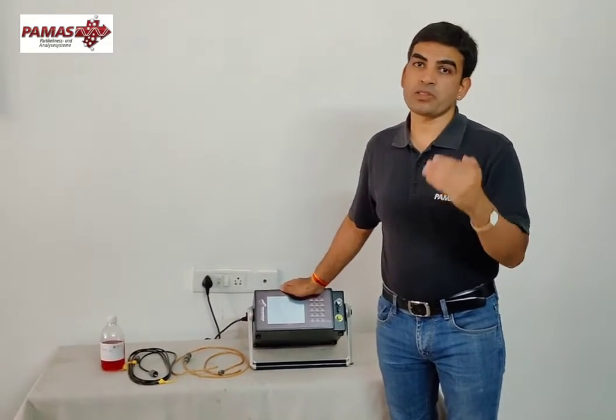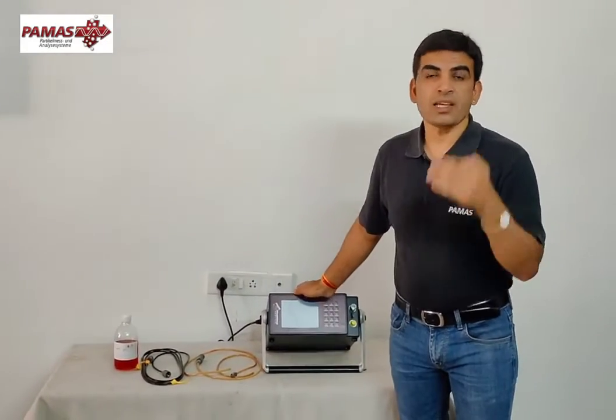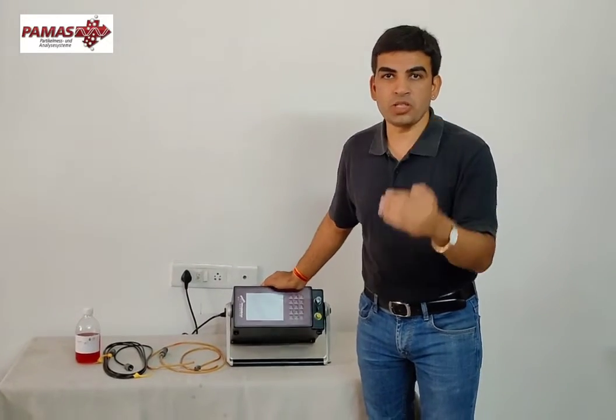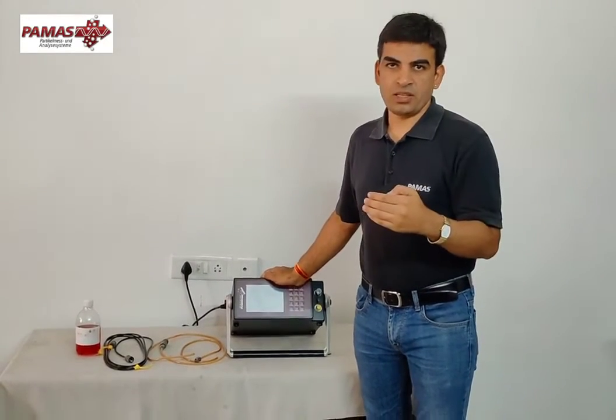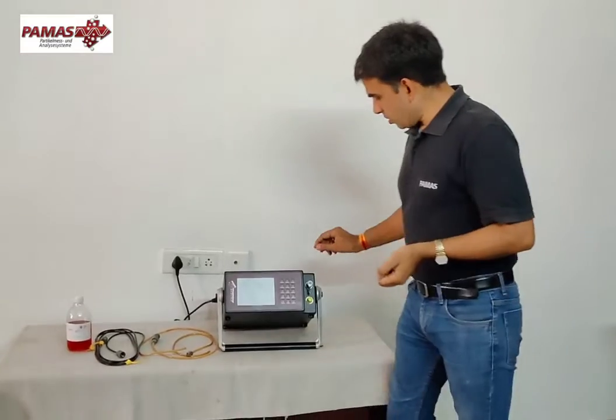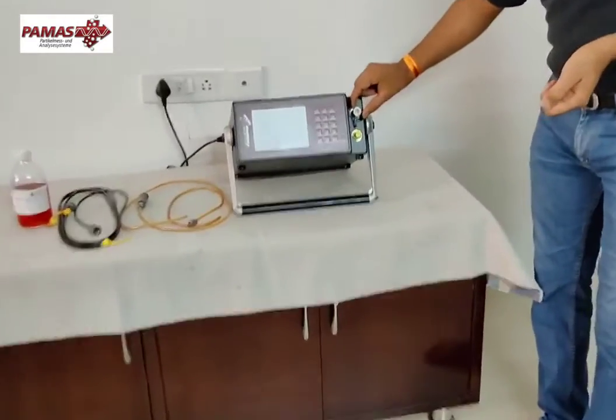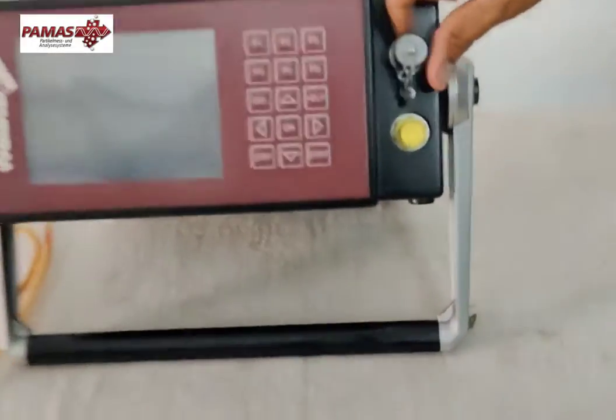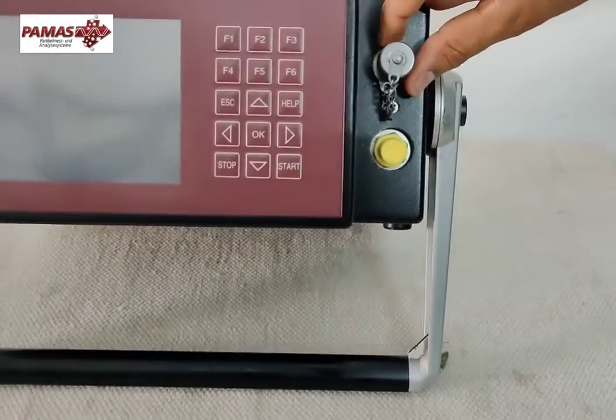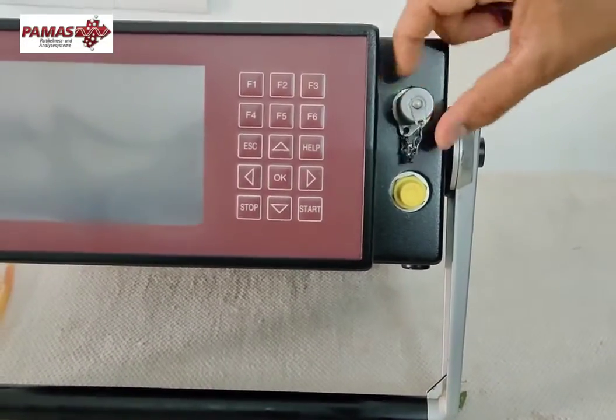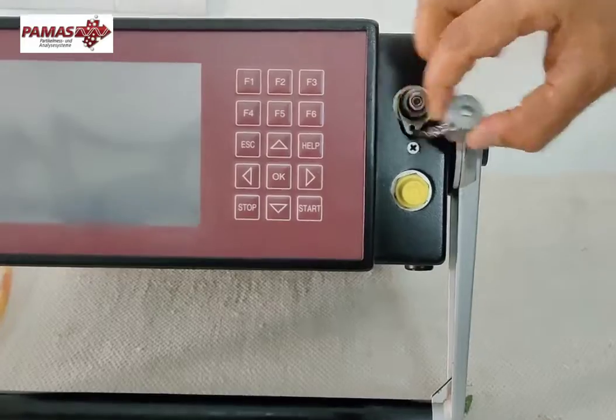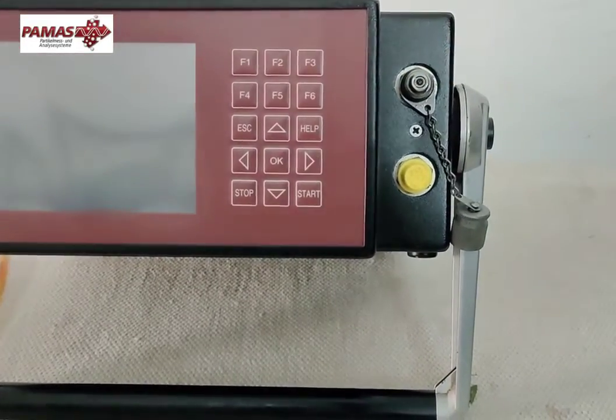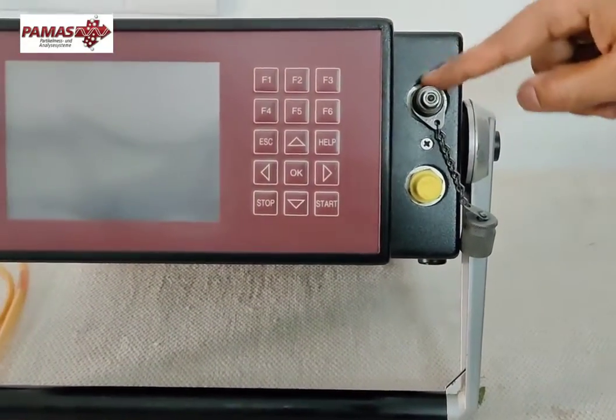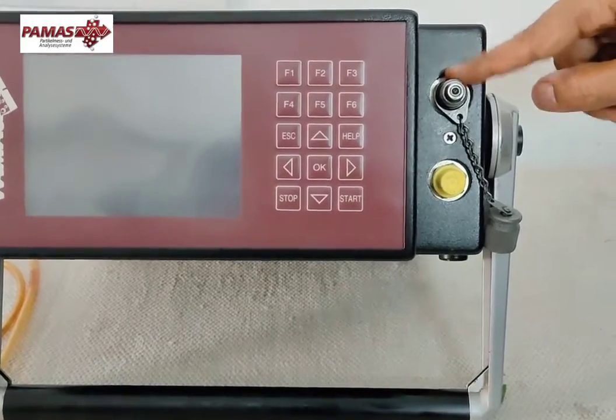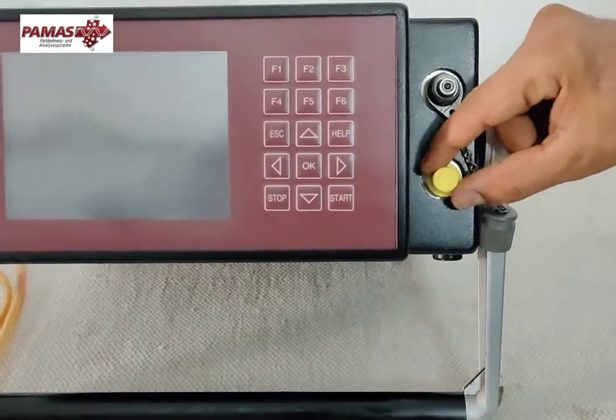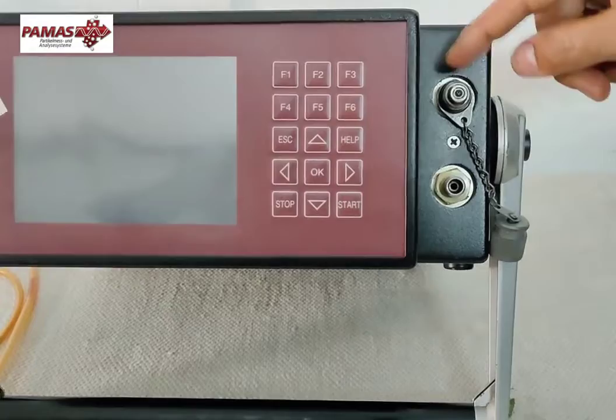You will get reports in ISO, NAS, SAE, GOST, GJB and many others. So if I show you, these are the inlet outlet connectors here. For example, if you want to connect the instrument to any live hydraulic system, you just simply connect this port to the hydraulic system. You can use any pressure up to 420 bar. This port is the low pressure input. This is the high pressure input.